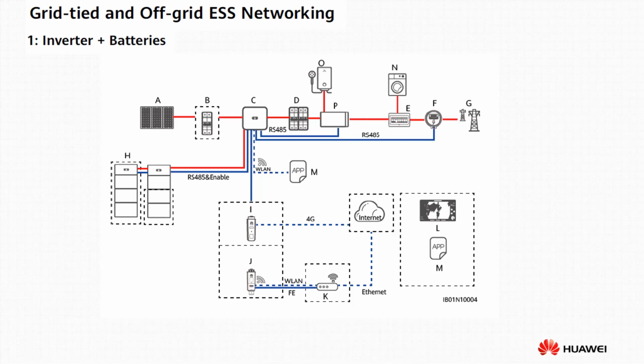So you've got one inverter with battery, then you've got your setup, and then power coming from the grid. Your meter measures the whole premises before you supply everything, because the meter is the one which is responsible to give the set point for the inverter to produce. So the meter positioning is quite important in hybrid scenarios.